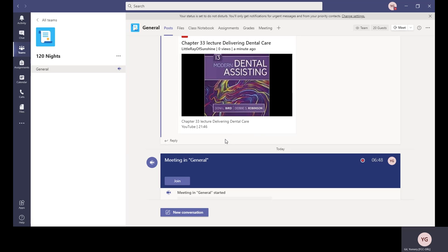It's operated by air pressure, and it operates at speeds as high as 450,000 rotations per minute. It maintains a water coolant system, because we said anytime the dentist works with the high-speed, it shoots water because it has to keep the tooth cool so that you don't overheat the nerve of the tooth. And it has a friction grip locking system for rotary instruments. So these actually do have a little locking mechanism. Once you put the burr inside, it'll lock, and then you have to press a button, or sometimes a key if you're using older high speeds, in order to take the burr out.